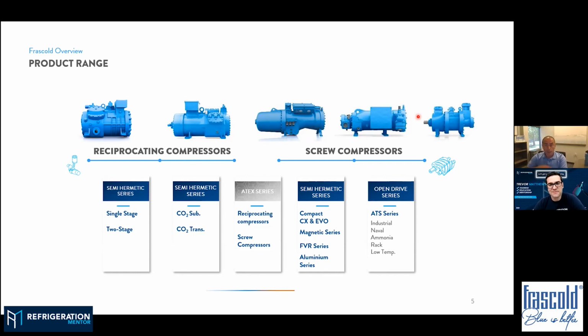Yes, sure. For this series of compressors, from the fractional HP up to the compact ones that go to 310 HP, these compressors are already rated for propane, and we've made a lot of applications here in the United States. Believe it or not, it was much easier than I thought. Especially the last one we started up, with this compact screw compressor - actually three of them with 70 pounds of propane per circuit.